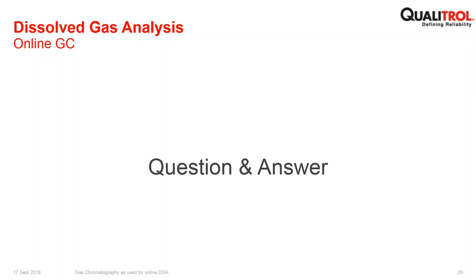With the TONE system, it does not alarm on, let's say, ppm or rate of change. It alarms on a combination of conditions that result in a diagnosis. So essentially it takes that necessity away from the user to go and view the ppm data, view the rate of change data, and make a decision. And this artificial neural network system will give you an alarm on an actual fault. So different systems, but again, a lot of it is driven at a personal decision-making level in a utility.